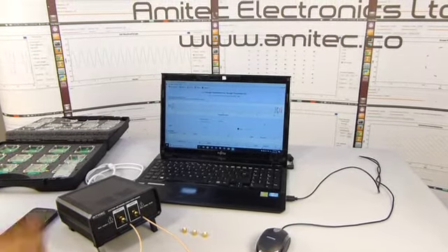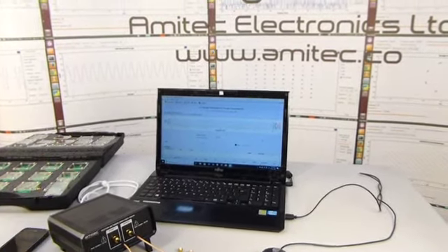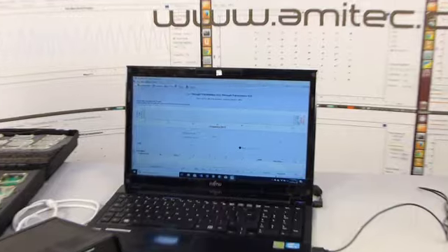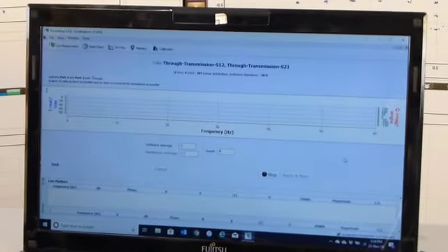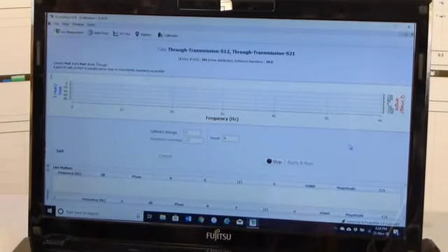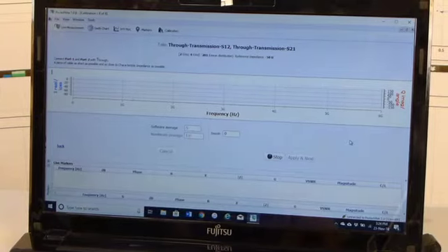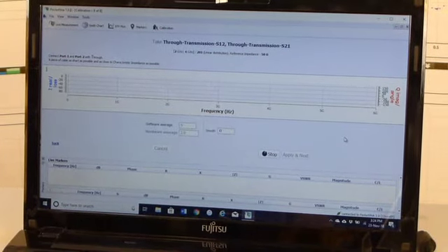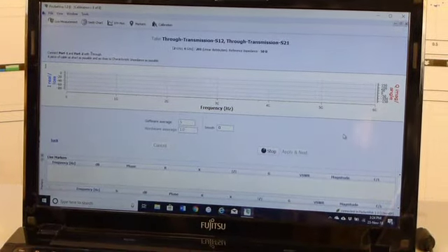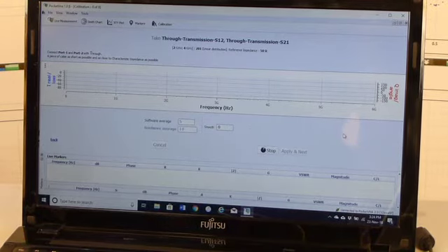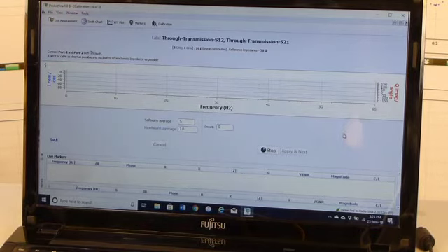Now, if you had observed, when we started this calibration, it said SLOT. As you can see, S is for short, L for load, here load means 50 ohms, and O is open, and T is through.